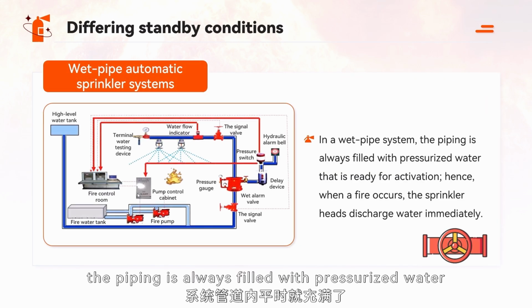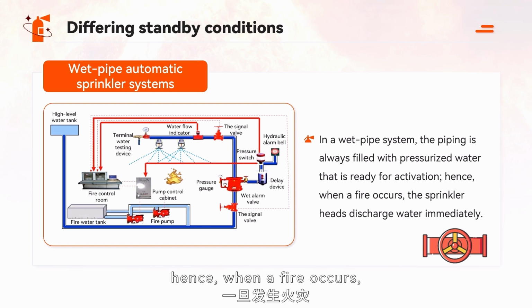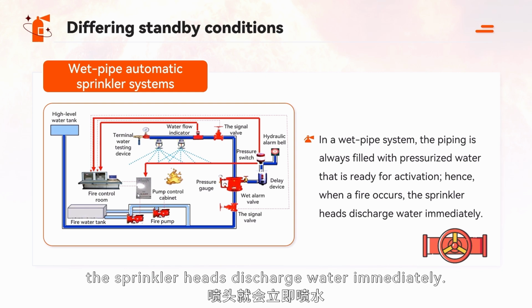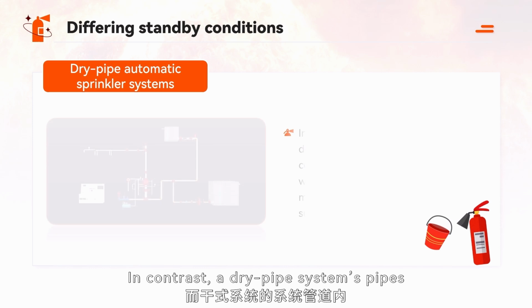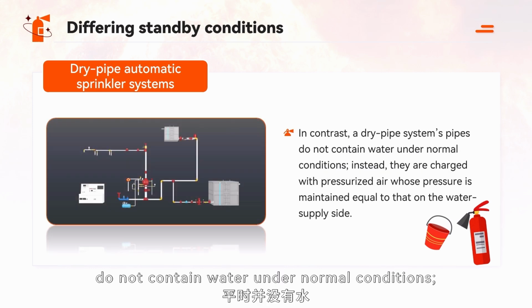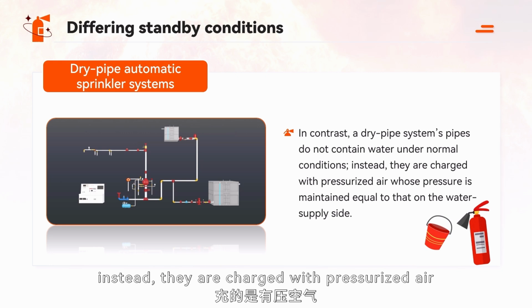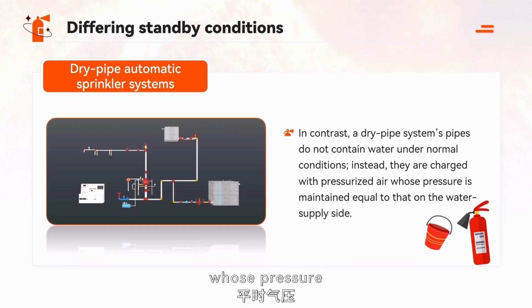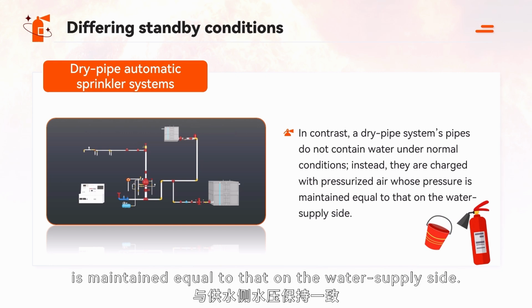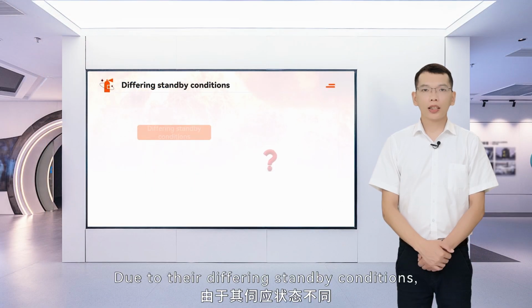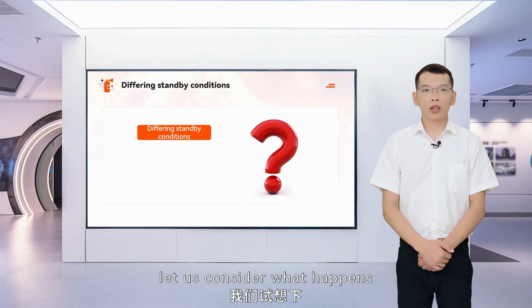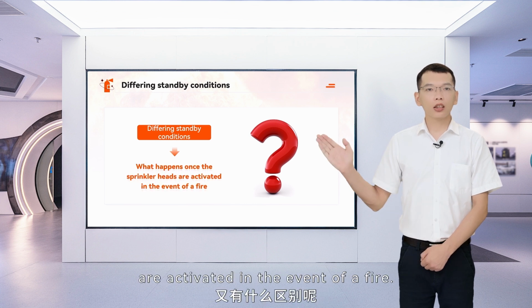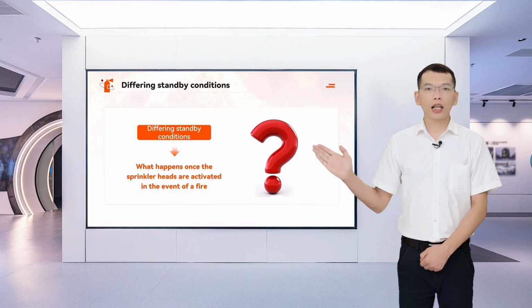First, their standby states differ. In a wet pipe system, the piping is always filled with pressurized water that is ready for activation. Hence, when a fire occurs, the sprinkler heads discharge water immediately. In contrast, a dry pipe system's pipes do not contain water under normal conditions. Instead, they are charged with pressurized air whose pressure is maintained equal to that on the water supply side. Due to their differing standby conditions, let us consider what happens once the sprinkler heads are activated in the event of a fire.